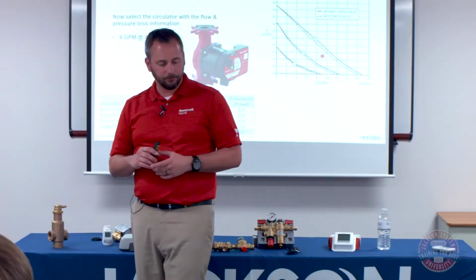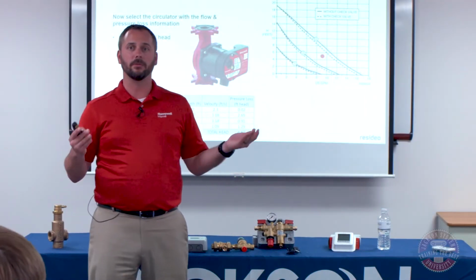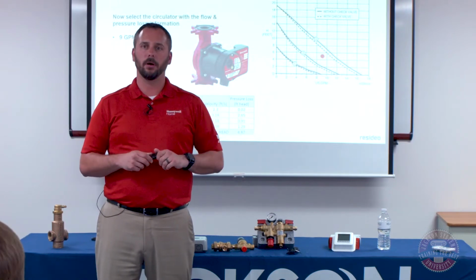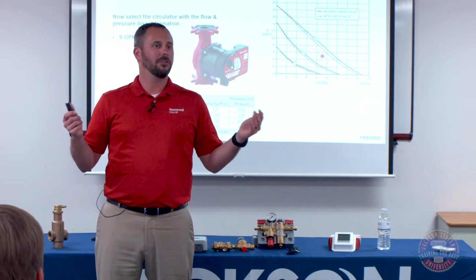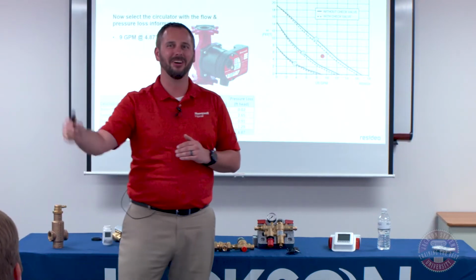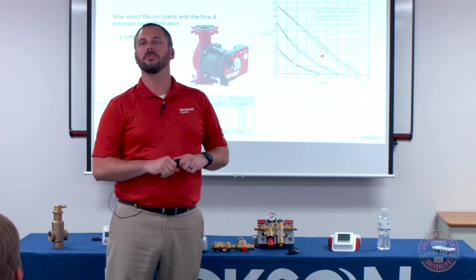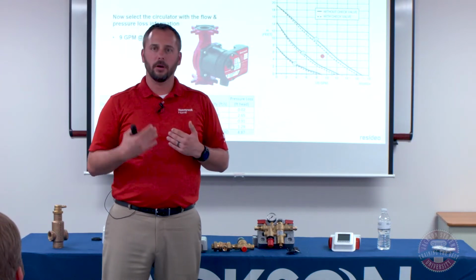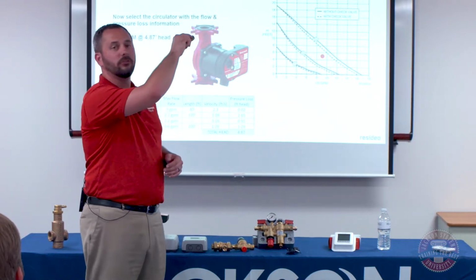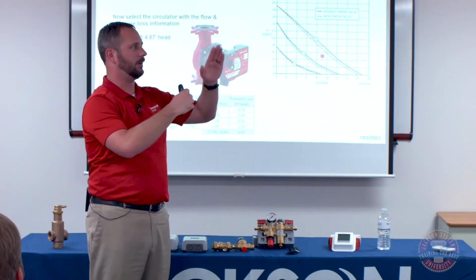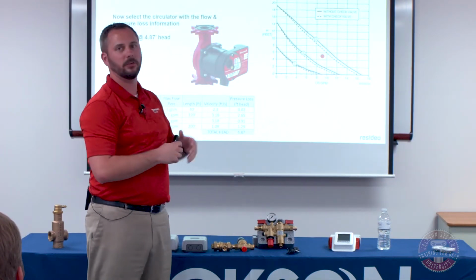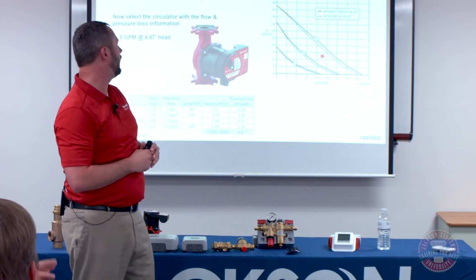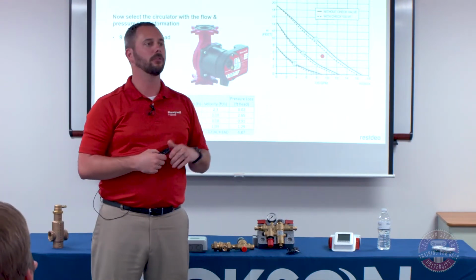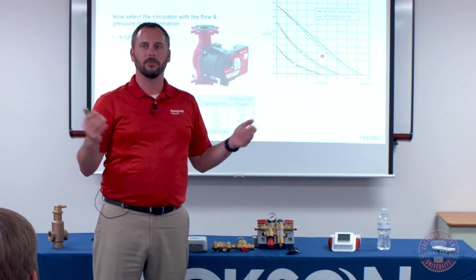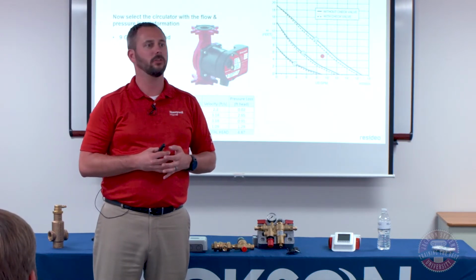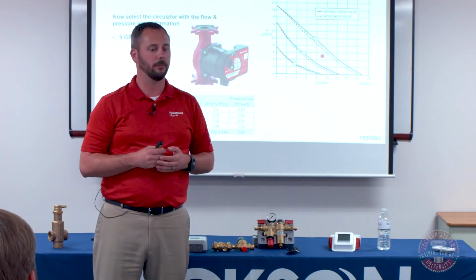And when we place that, you basically just summarize it all there. You've got your flow rate and your head pressure. You place a dot on the pump curve. You need to go to the curve that's above the pump curve. So where we've got that red dot, that's basically where the system needs to operate. As we're operating and running, there's actually an operational curve that tracks that. It looks exactly like a pump curve but flipped on top of each other. So that pump's going to operate roughly at 10 gallons a minute at 6 feet of head because there's a pressure curve that it follows. So as far as sizing a pump, you just find the pump that most closely fits the duty point that you come up with for the system.